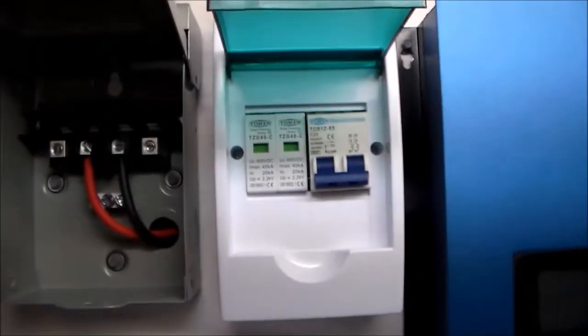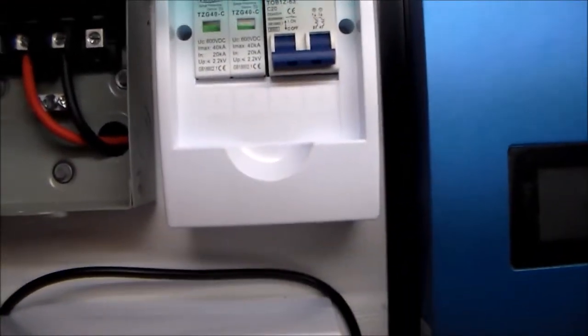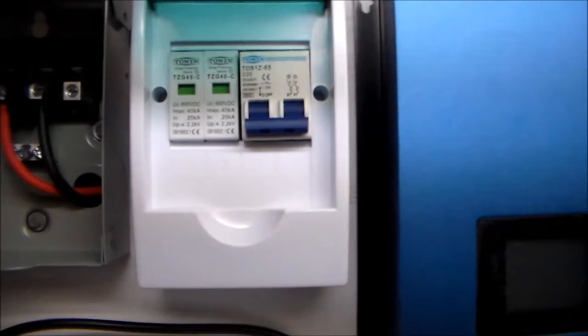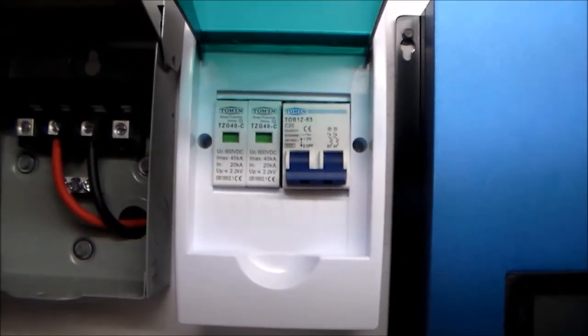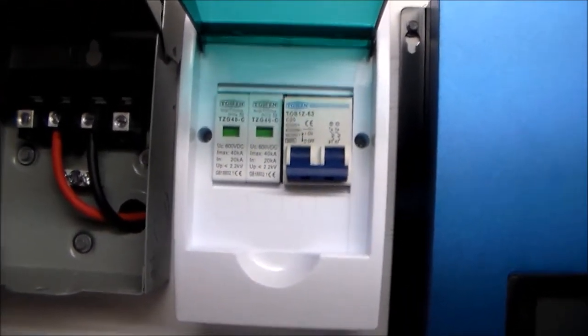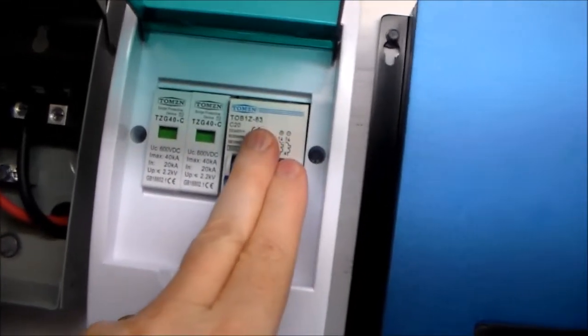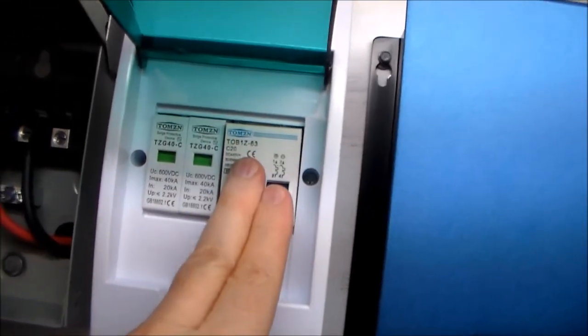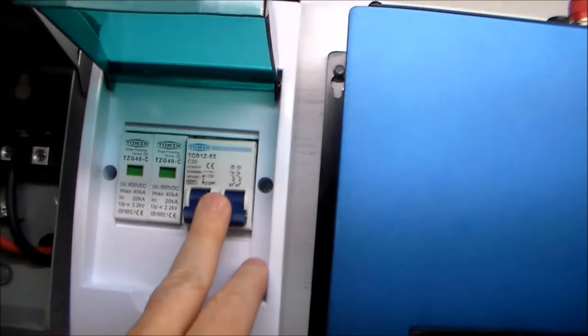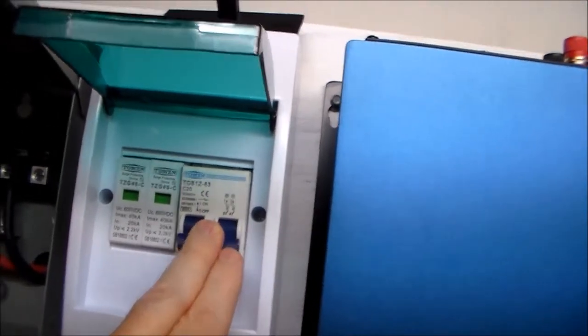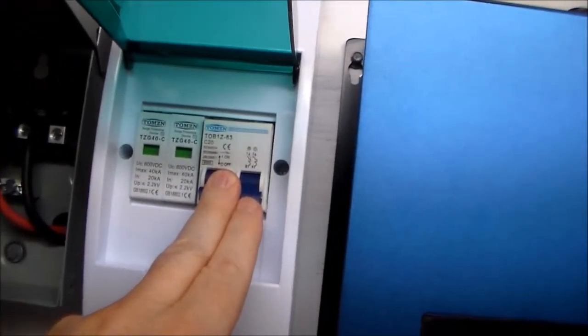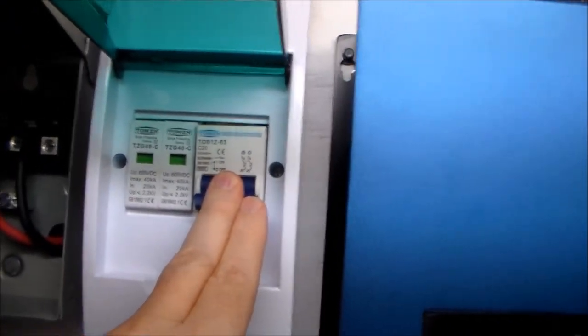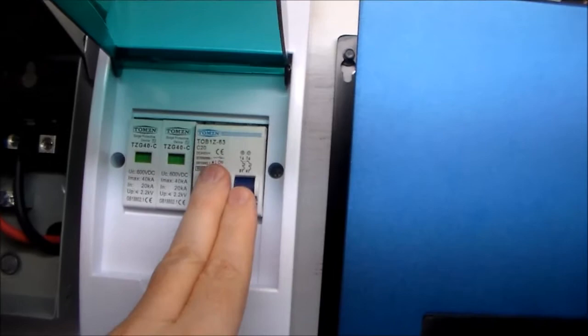Doing the math we did earlier, I know I should have at max power coming from the panels about 17 amps. So I installed a 20 amp circuit breaker. These usually come in increments of 5, so 15 would have been too low, and 20 is the next step up.